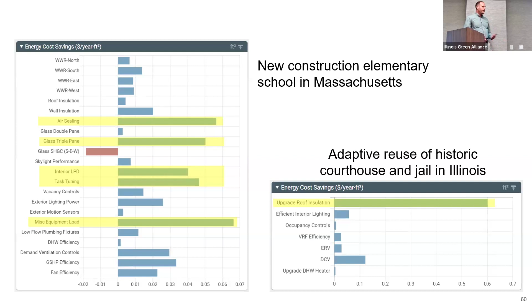So task tuning is the second step: going into that control system and saying the power output doesn't need to be 100%, it can be 87%. Then you're hitting exactly 30 foot-candles with your light fixtures and you save quite a bit of energy. It's important that you specify that the lighting contractor should actually do that — if you're going to model it, it's got to be in the document somewhere. It's essentially a free measure these days, but it's got to be in someone's scope of work.